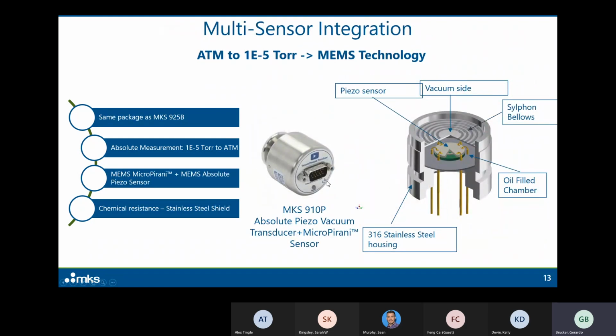We were able to use MEMS technology also in the 910P, which is a combination of both a micropirani and an absolute piezo sensor. And again, this is a very small device. This is a MEMS device. And the advantage of this device is that now we combine in a single sensor a MEMS micropirani and an absolute piezo sensor, which comes with a stainless steel encasing. And because of the stainless steel case, we have a very large chemical resistance. So it's a great product to use to increase the accuracy relative to the Pirani sensor above 10 torr, and also if you're going to be exposed to high pressures of reactive chemicals that might actually interfere with the hot sensor wire.